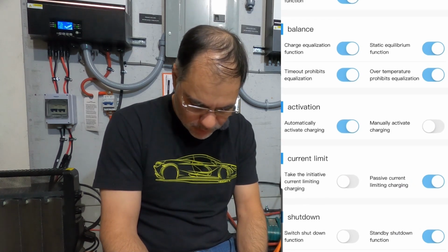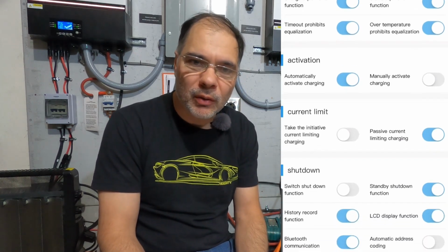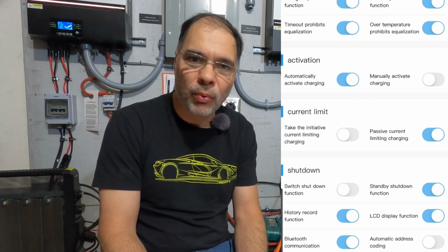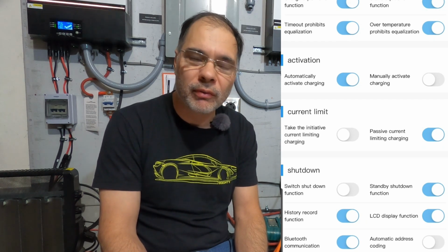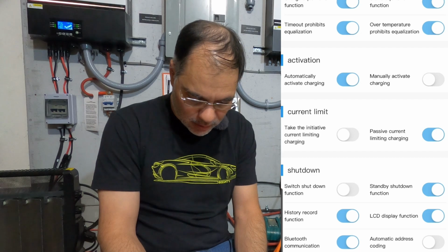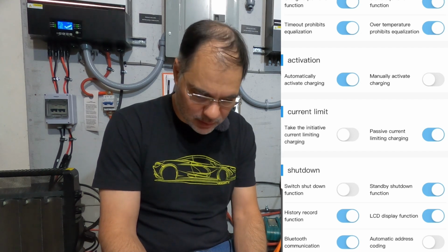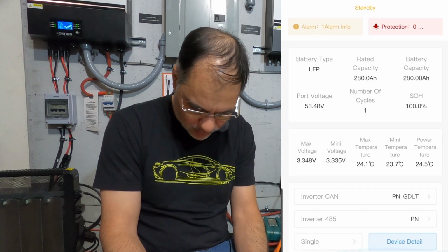But in either case, it's not going to work until the voltage gets above 3.40 volts per cell on any one cell. So let's plug it up to the charger. We're going to set the charger for 10 amps, 54.4 volts, or 3.40 volts per cell, and see if we can bump it up slowly. Let's check our delta really quick.